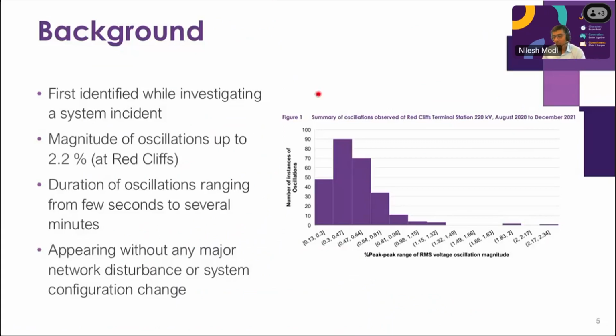Let me give a bit of background on the 17 Hertz oscillation. It was first identified as a byproduct of investigating a system incident. Since then, AEMO has been closely monitoring that part of the network through high resolution PMU measurements. What we have observed is that the magnitude of this oscillation has been varying. At one of the nodes, we have seen a maximum of 2.2% oscillation peak to peak, but most of the time the oscillations were in the range of 0.5% peak to peak. The interesting bit about these oscillations was that their duration ranged from a few seconds to several minutes, so often it comes on and goes off. And it was appearing without any major disturbance or system configuration change, so it was very difficult to identify the cause because there wasn't any clear correlation with a system disturbance.